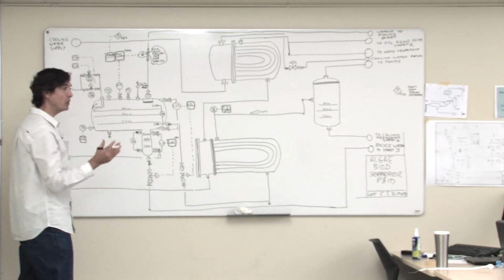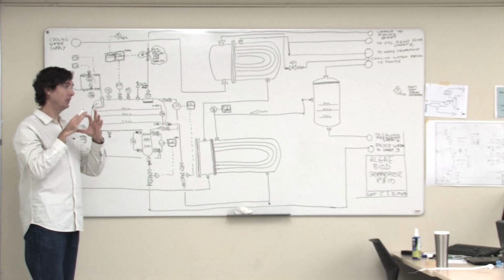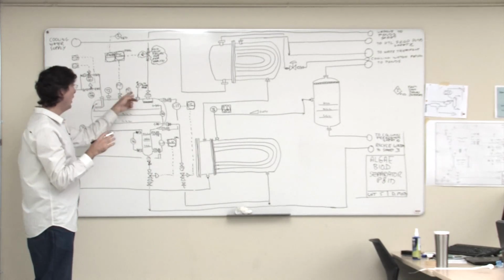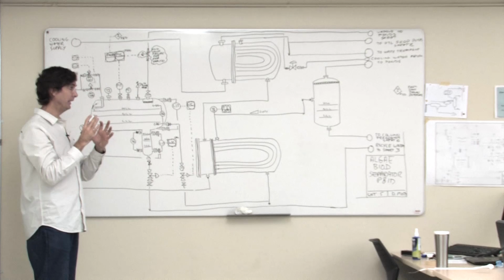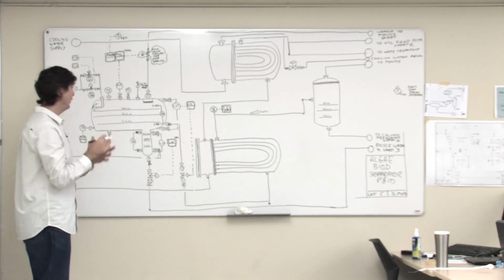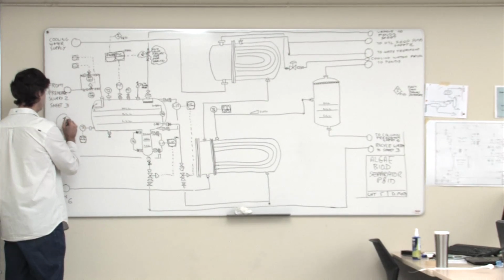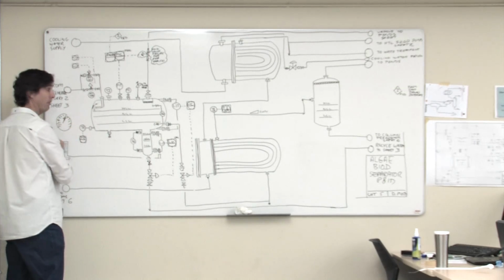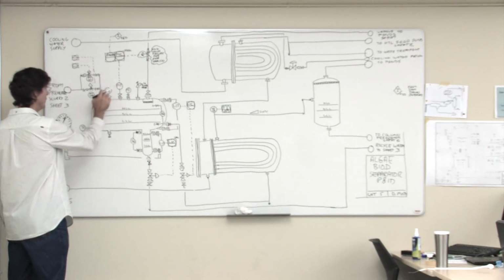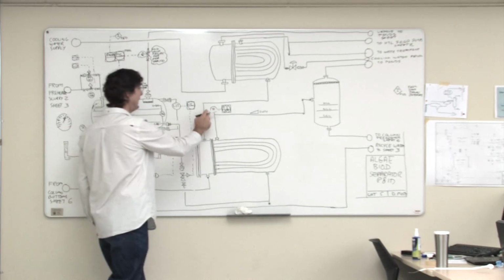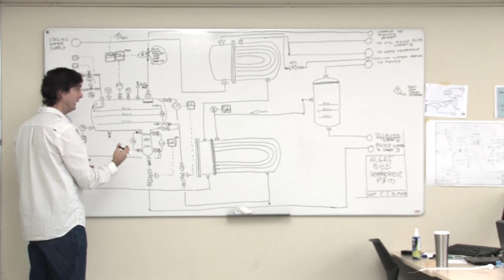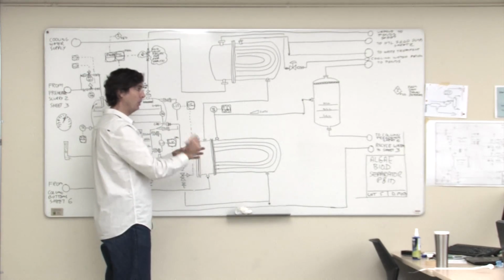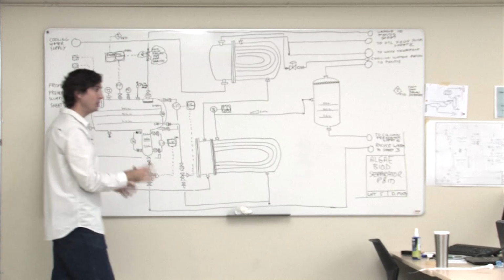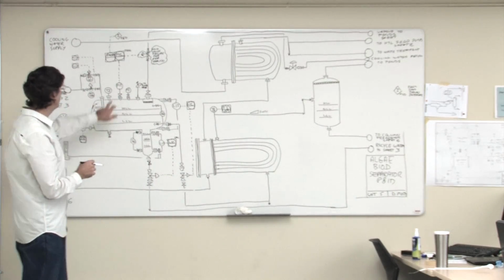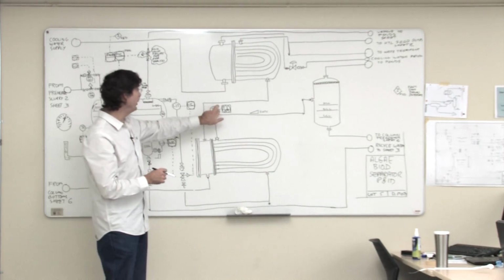A temperature gauge is literally like a thermometer, the same way a PI is a pressure gauge that just reads locally - it's a dial, like a thermometer. A TE doesn't have any indication, it's just a blind thermocouple or RTD, and it has to be wired back to the DCS before you can actually see it. So this you can actually read when standing out by the tank. That you cannot.